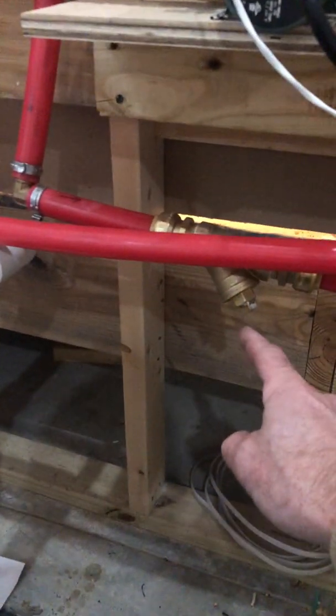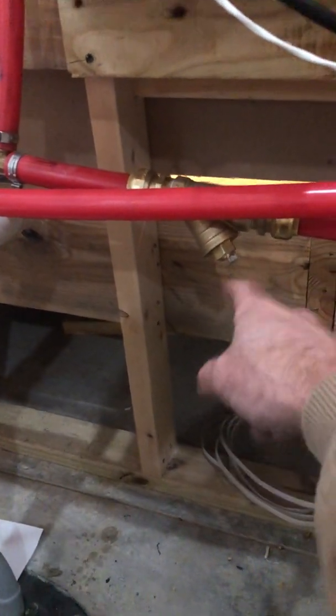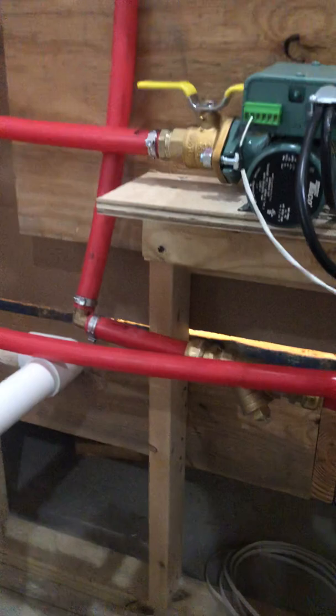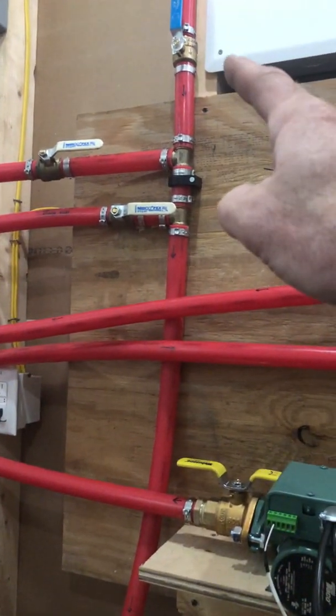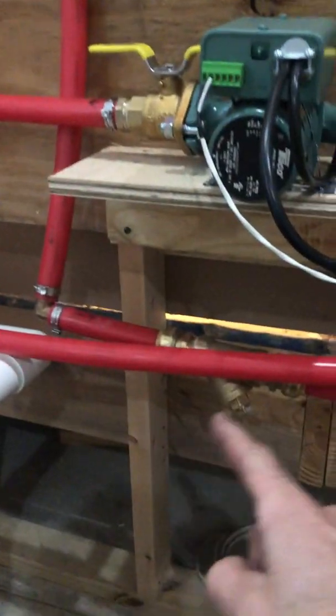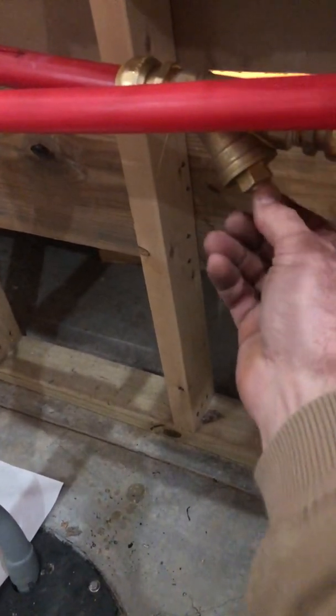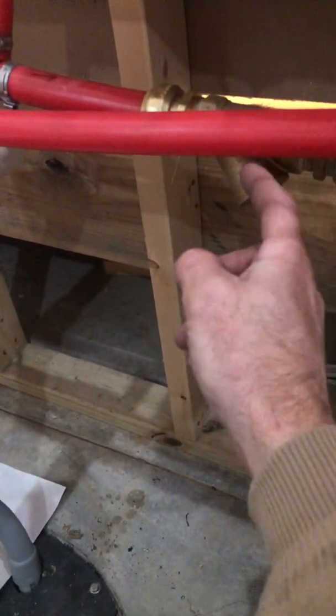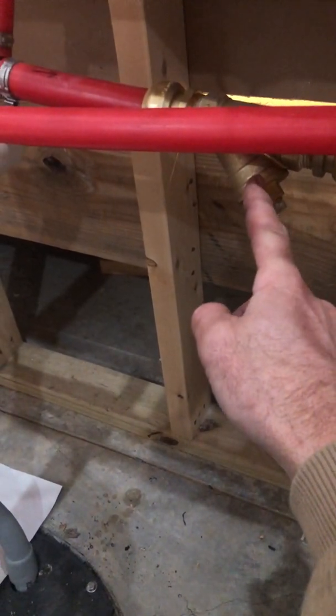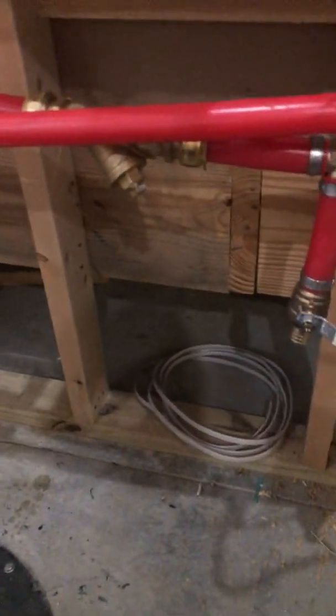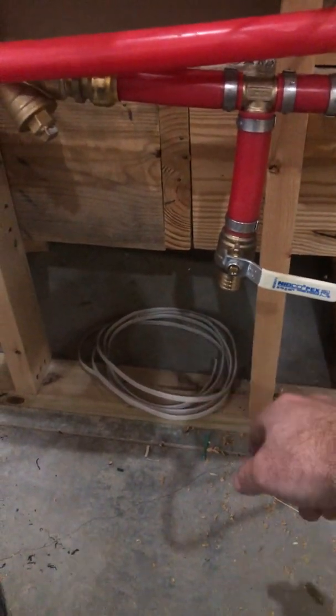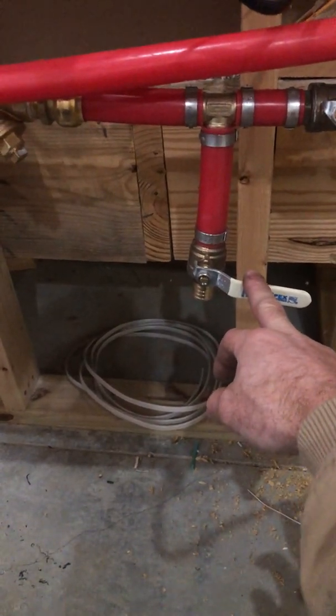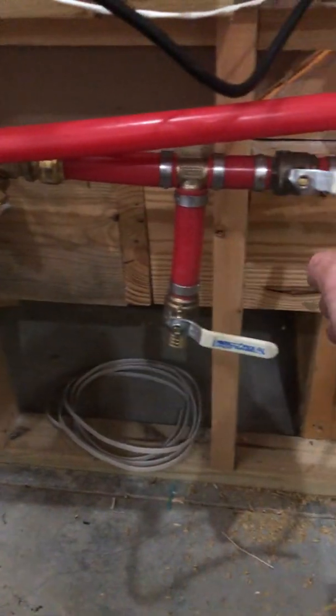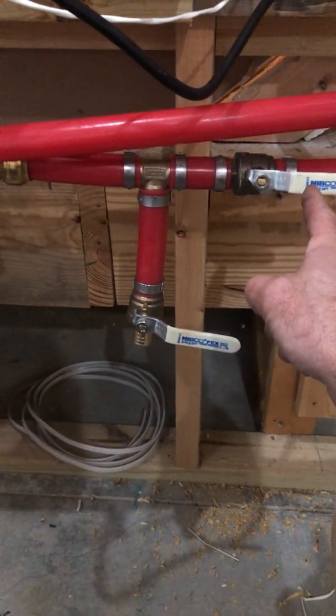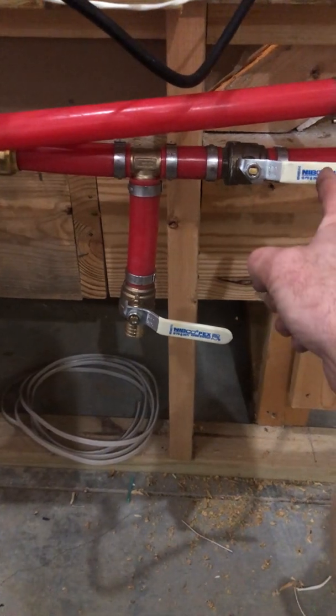I did put a Y strainer, and so any particulates in the system, I can lock off the valves up here so I don't lose a ton of water, and I can take this bottom plate or this cap off, and then any solids that were flowing through, this has a metal screen inside it, and yeah, the solids will come on out. And then I put in a drain here, which I'll put a water hose connection or something on there in the future. And then again, to take this off, I needed to be able to stop it from backflowing and flooding out too much water, so I put another ball valve here.